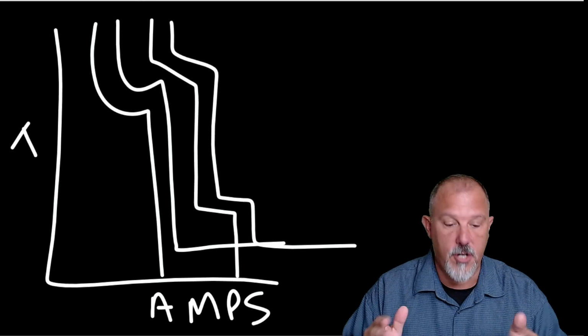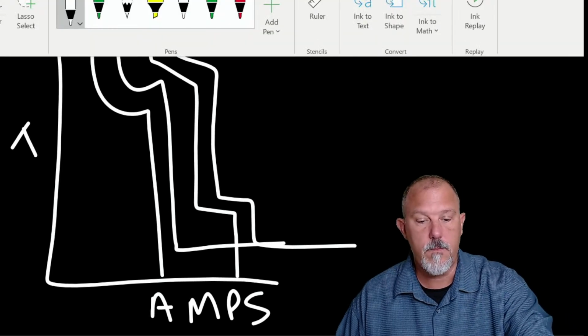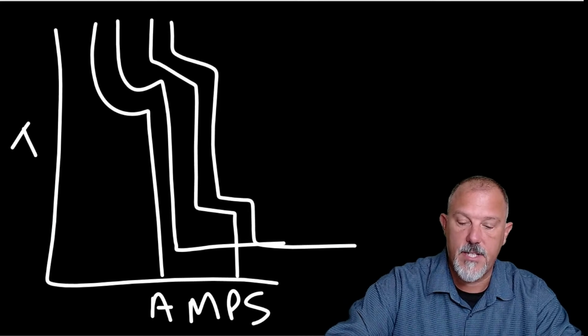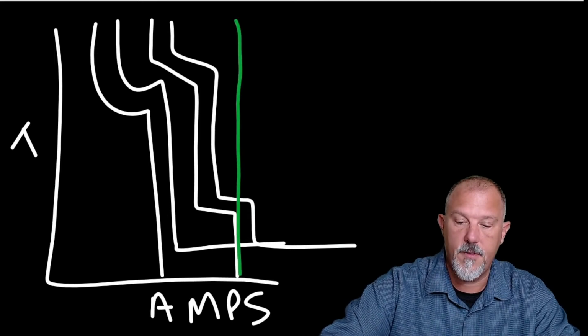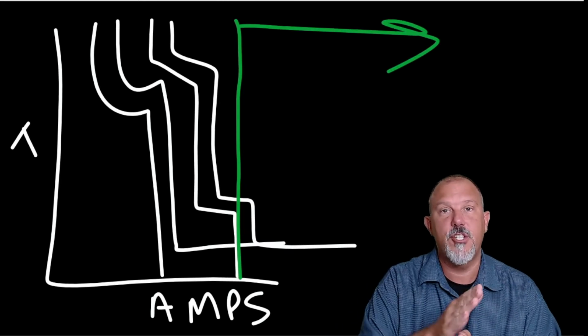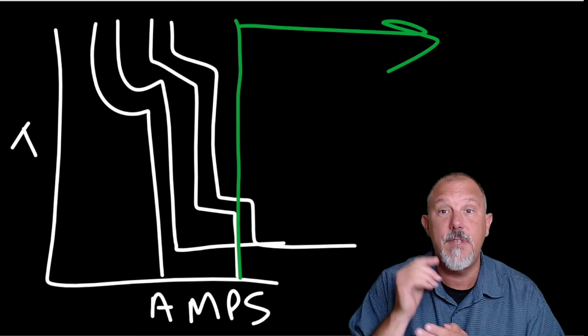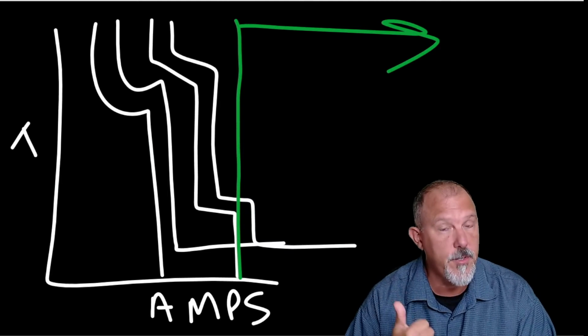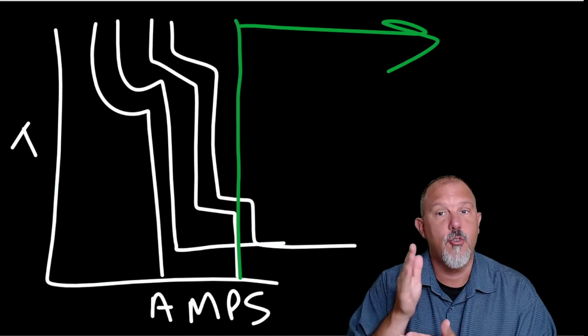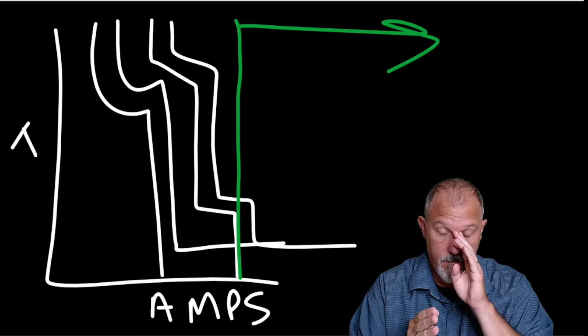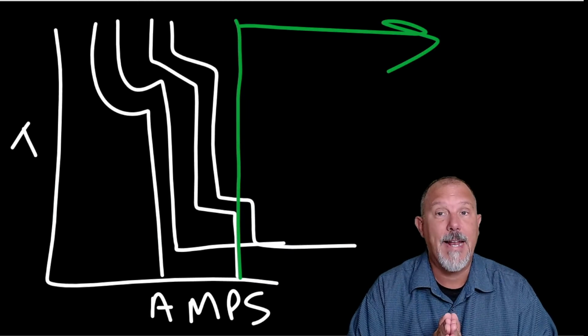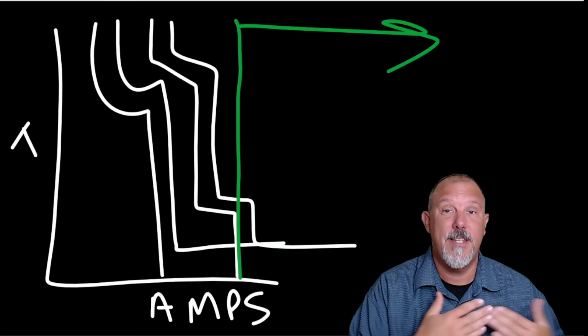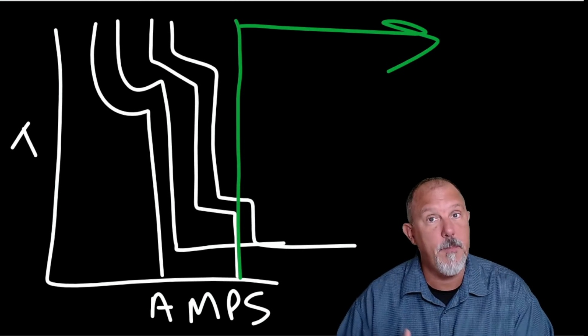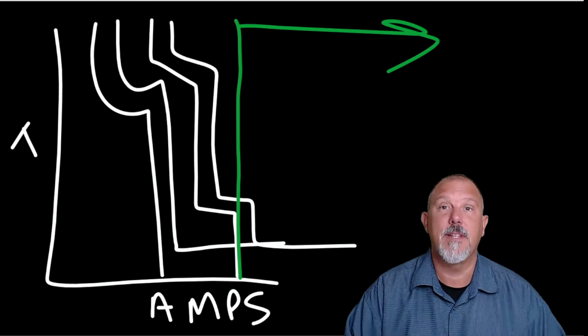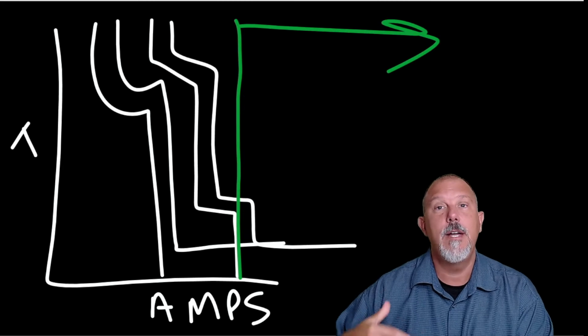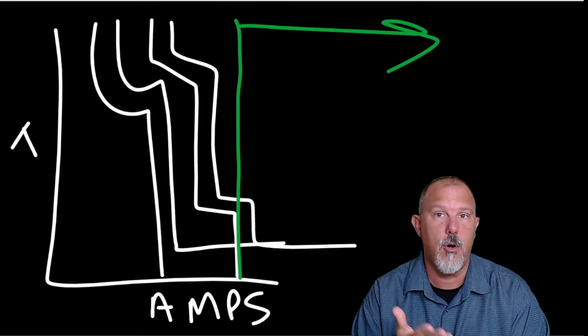What we know from these two curves is that if I have a fault current that is anywhere greater than this point, and that green line shows you the instantaneous pickup of the upstream circuit breaker. If my fault currents are greater than that pickup point, then I can't rely on telling you whether or not the downstream breaker will clear and the upstream breaker will keep its contacts closed based upon the time current characteristic curves.